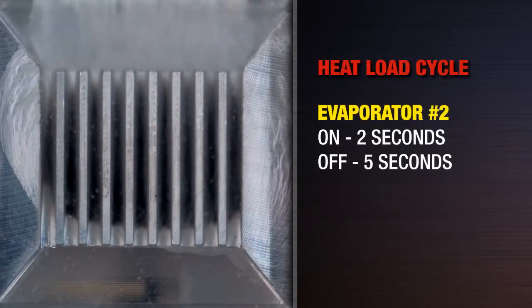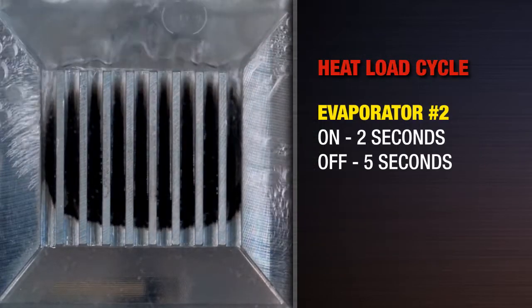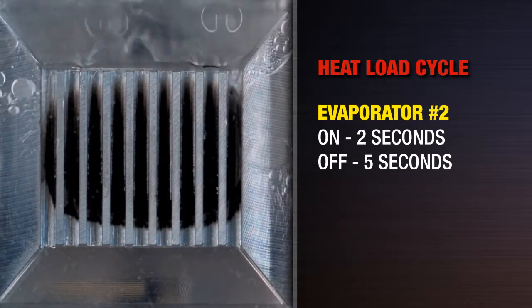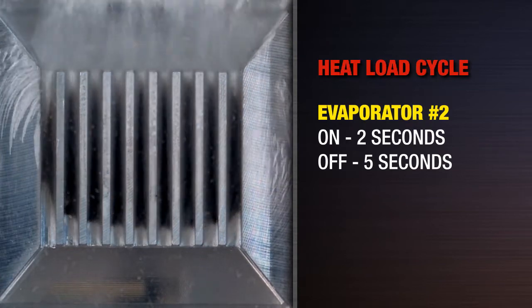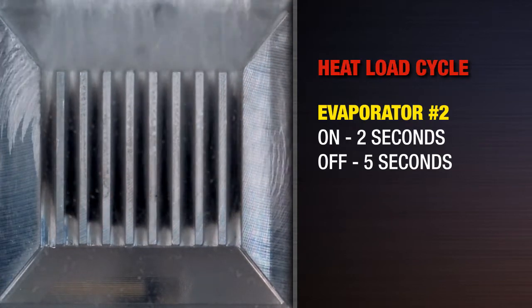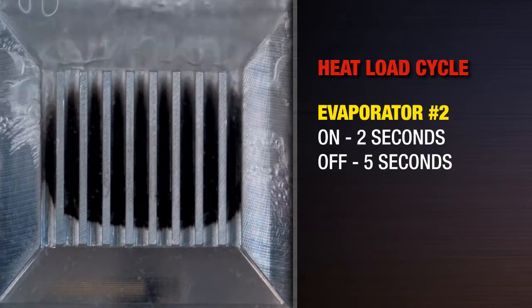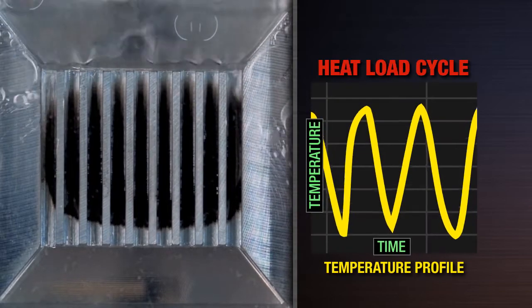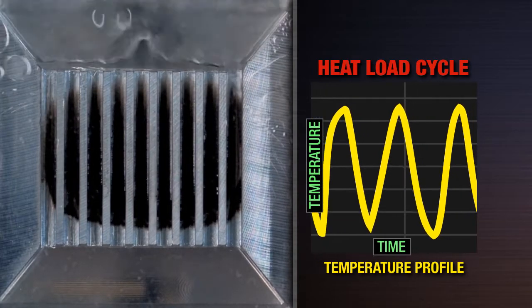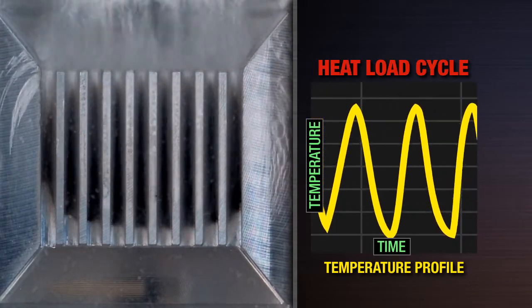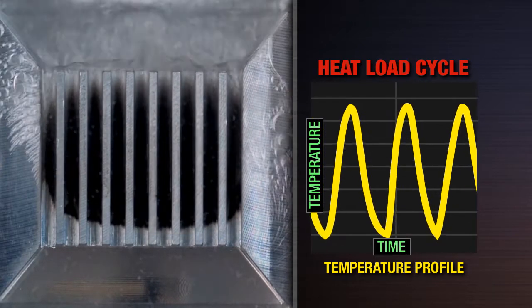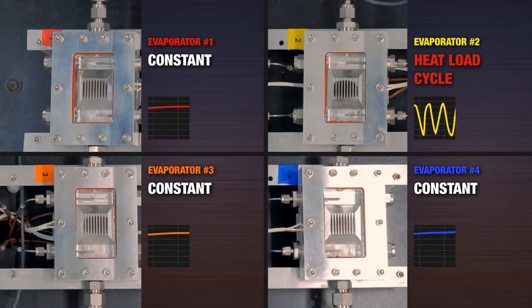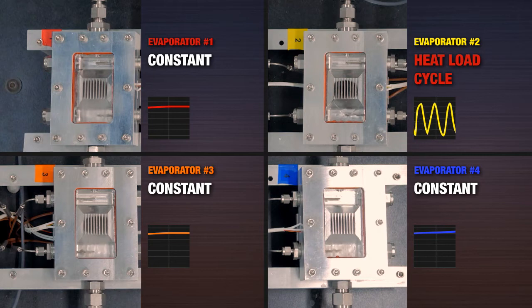Now we begin to cycle the heat load on evaporator number two. The heater is turned on for two seconds and off for five, simulating a variable heat load. You can observe that flow boiling at evaporator two becomes staggered and erratic as the temperature drops below the boiling point of the refrigerant. However, the performance of the other three evaporators remains stable.